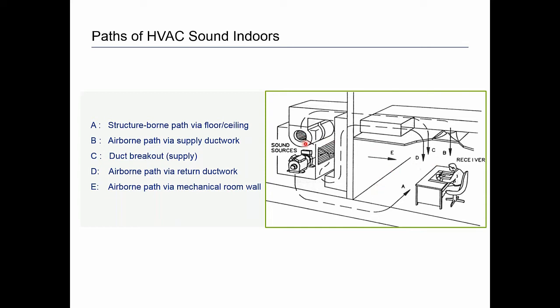The most obvious path is noise coming through the ductwork and passing out through the supply grills, but it can also come out of the return. Sound doesn't care whether it's going out the supply or the return — it will go both ways just as happily. The third way is breakout noise: sound at relatively high pressure moving through ducts can pass through the duct walls, so even a duct passing down a hallway with no local registers can radiate sound into a room. Finally, the structure itself allows noise to pass through it — a combination of airborne and structure-borne paths.